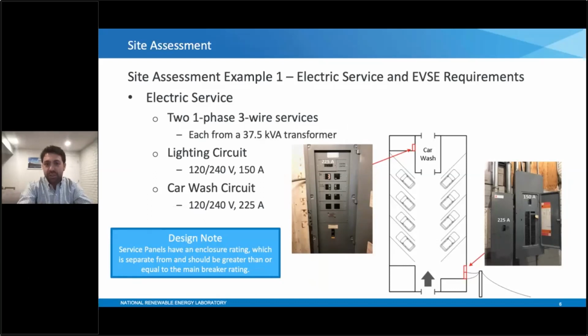There are 2 different service panels here. Highlighted in the bottom right, there's a 150 amp lighting load circuit - all the lights in this building are powered from this circuit. We also have a 225 amp circuit that powers the car wash in the back of the garage, so as vehicles exit, there's a separate circuit designed just to power that device. Both circuits operate on a 120/240 volt service, which provides a benefit because we get a slightly more powerful output from a level 2 station with 240 volts as opposed to just 208.